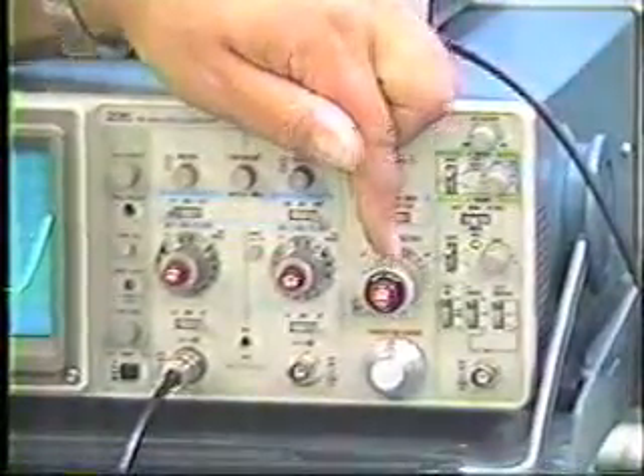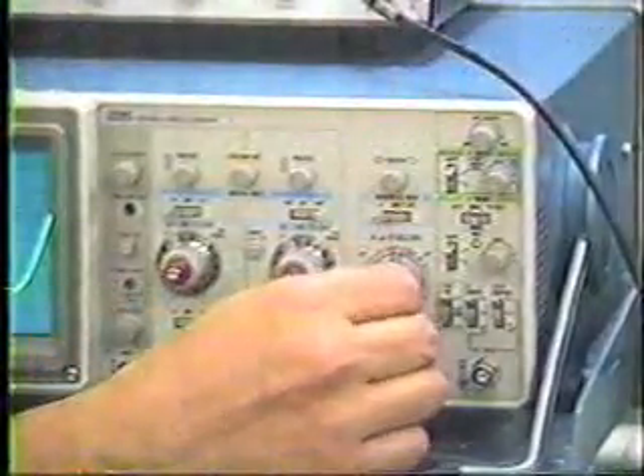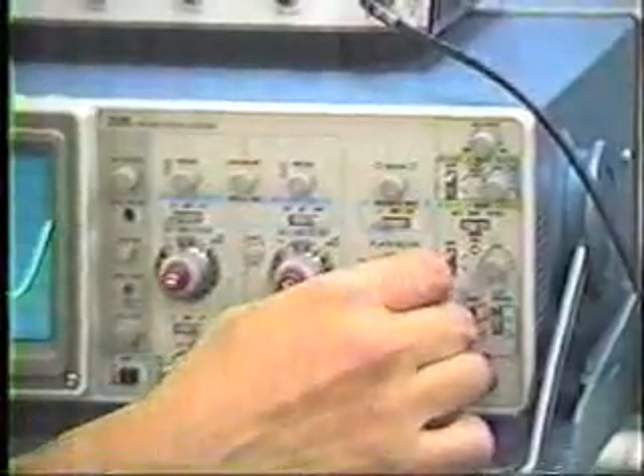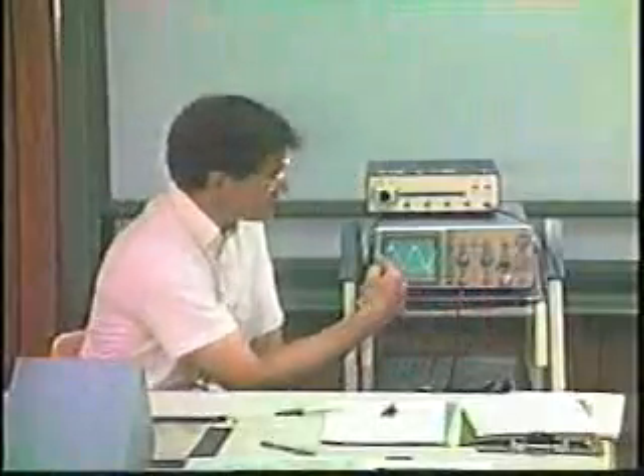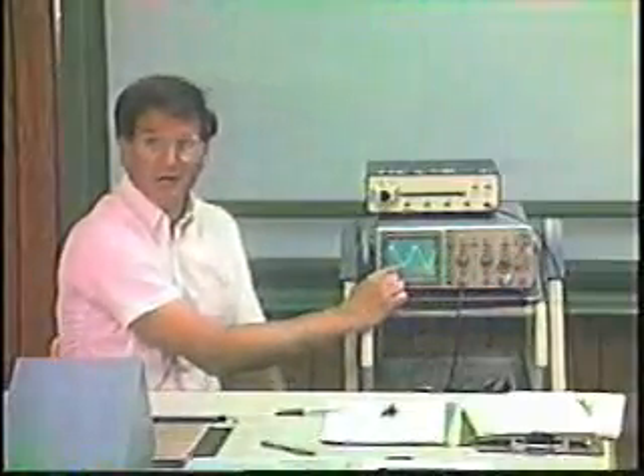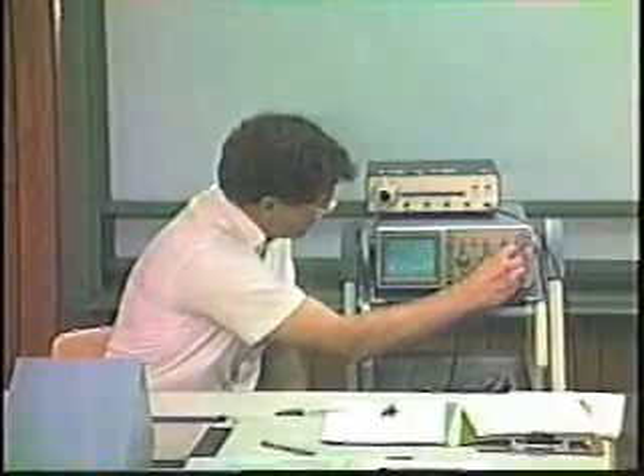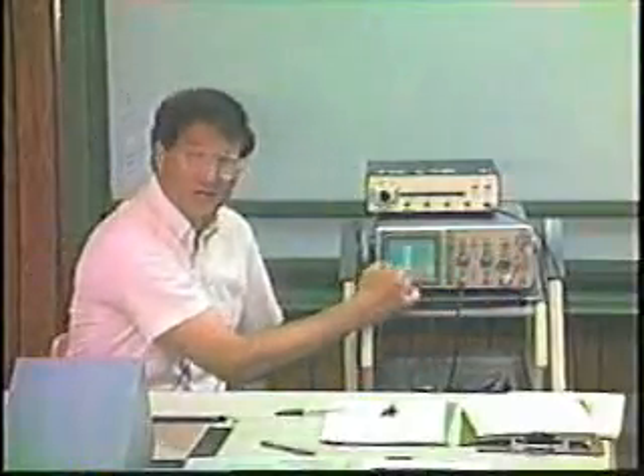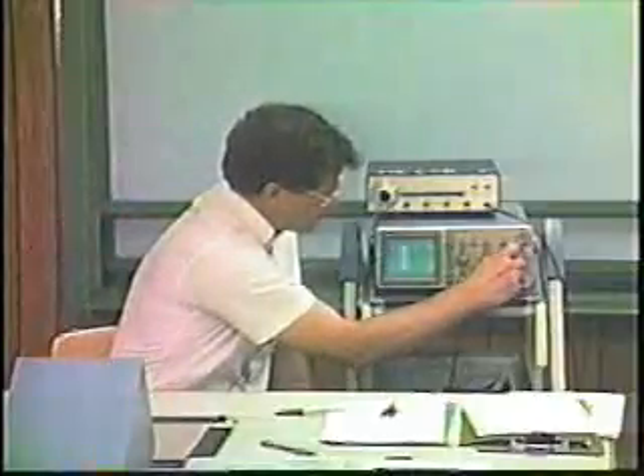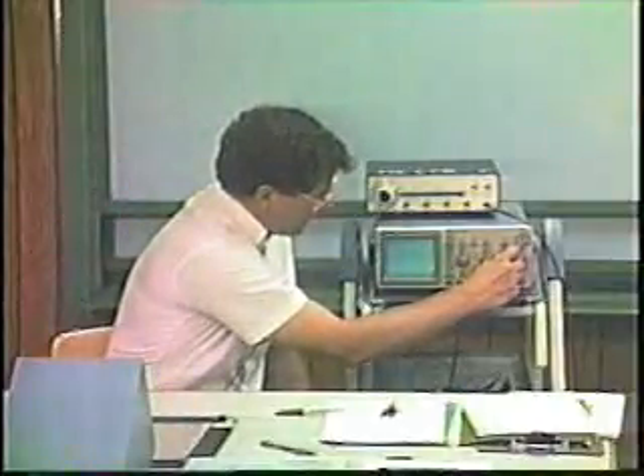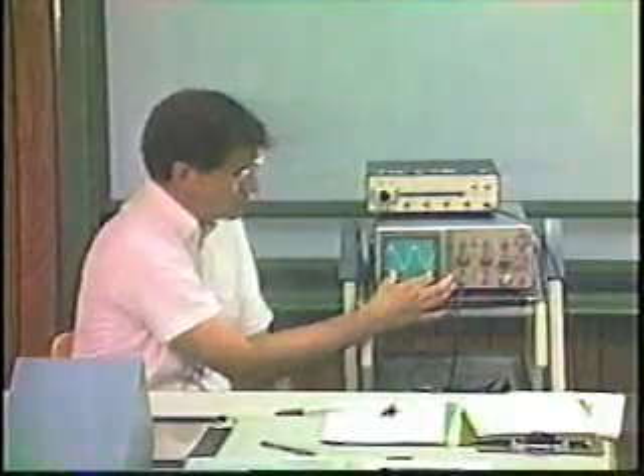And the time base, again, has a calibration in the center and a ring around the outside, which determines the rate at which the beam is sweeping across the CRT. Here you can't see it, but if I slow down the CRT to a low rate, then you can see the rate at which the electron beam is sweeping across the CRT. And so simply by changing that, I can change the calibration on time.